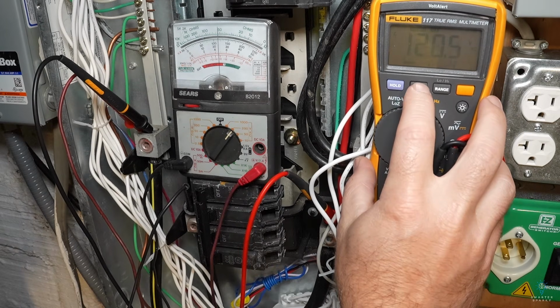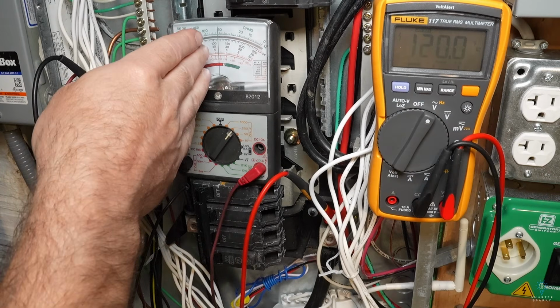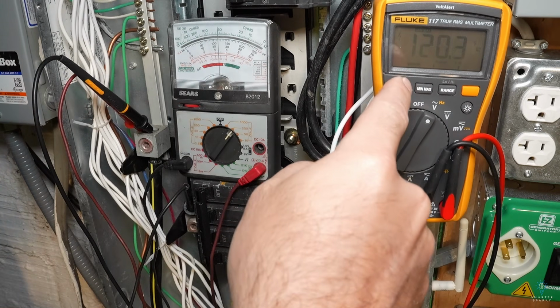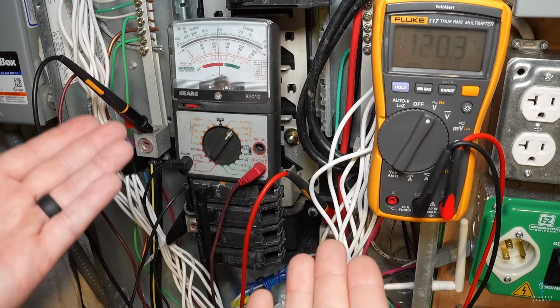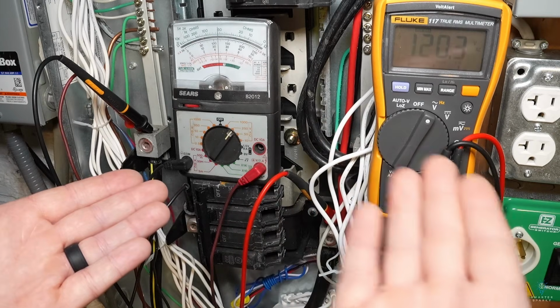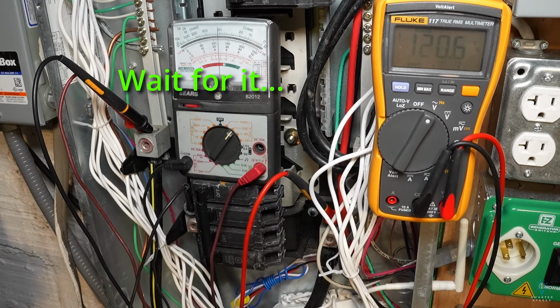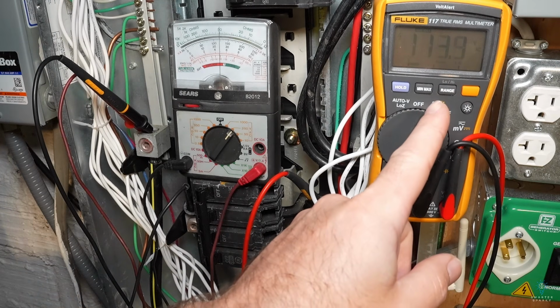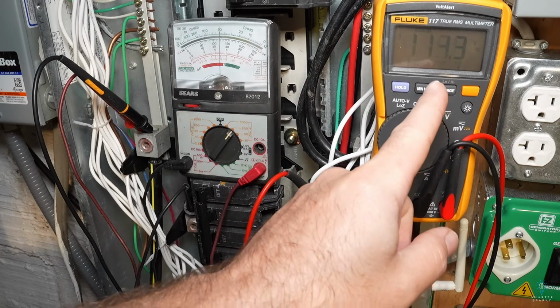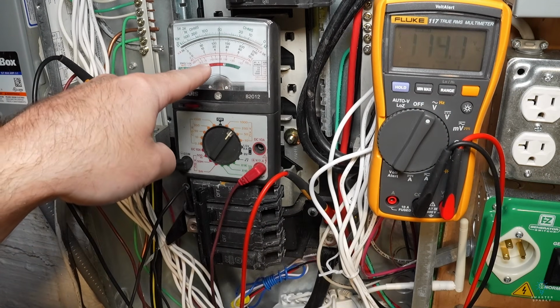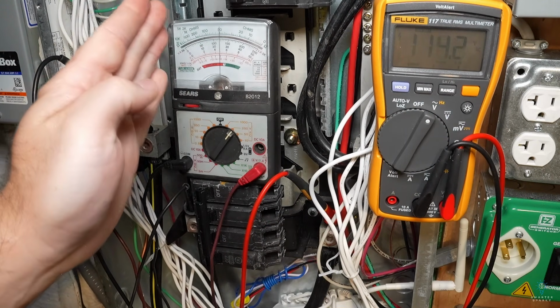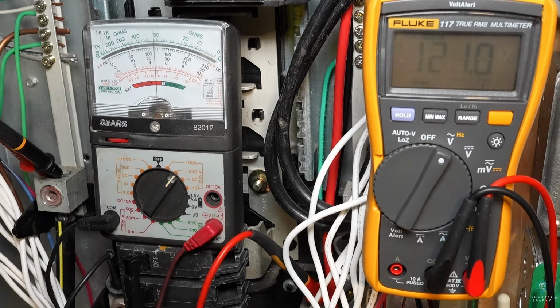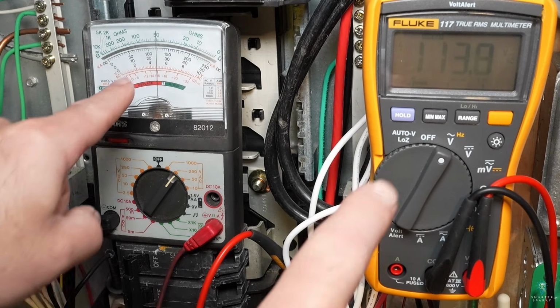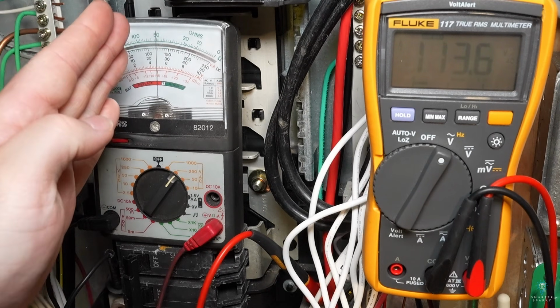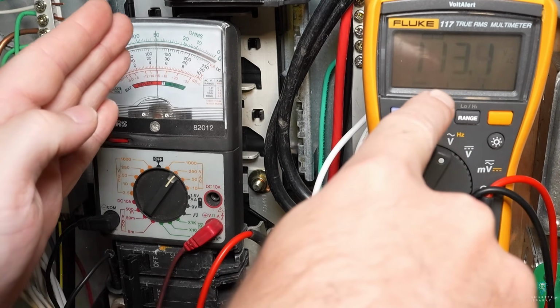Let's set this back to min-max. We got exactly 120 volts there. We've got exactly 120 volts there right now. So right now, line 1 to neutral is balanced with line 2 to neutral. So this voltage just dropped about 5 volts, and this voltage just raised about 5 volts. Let's wait for one of those. Oh, did you see that? That needle just moved up 5 volts, and this just dropped 5 volts.